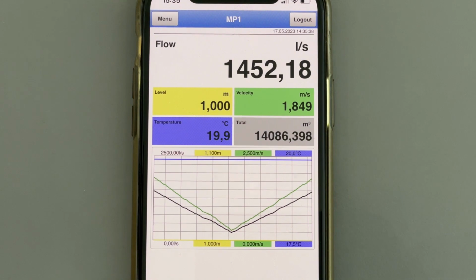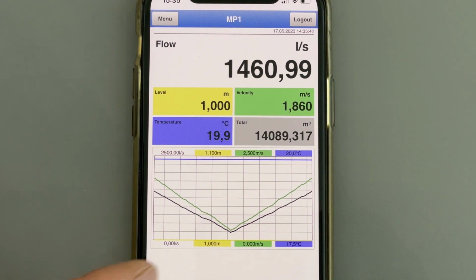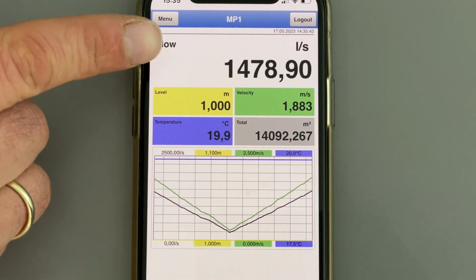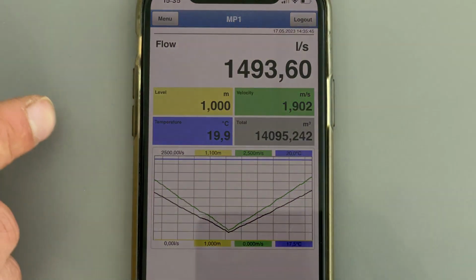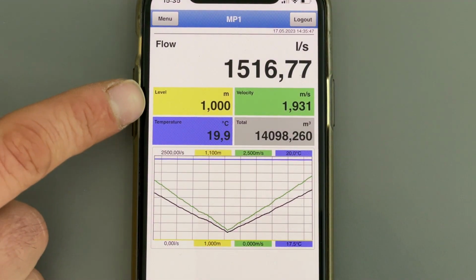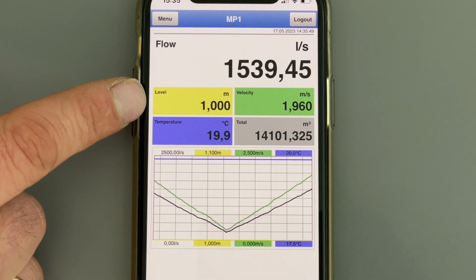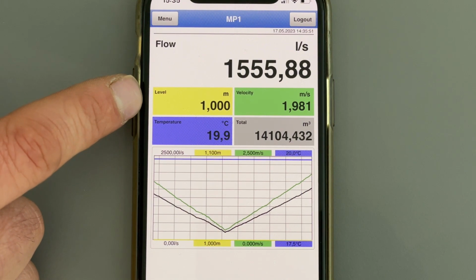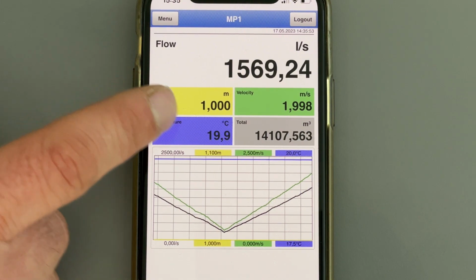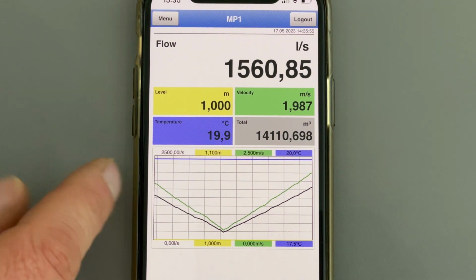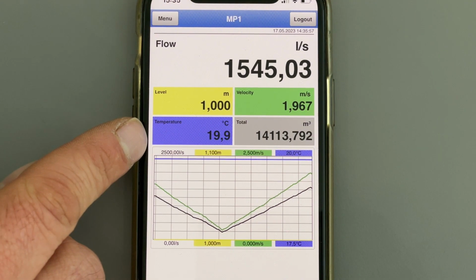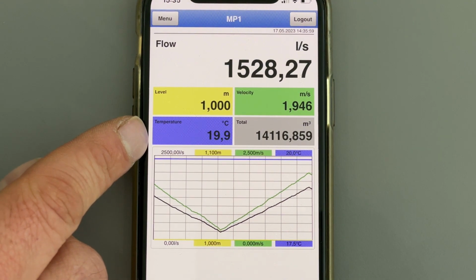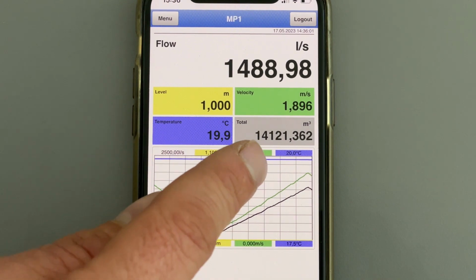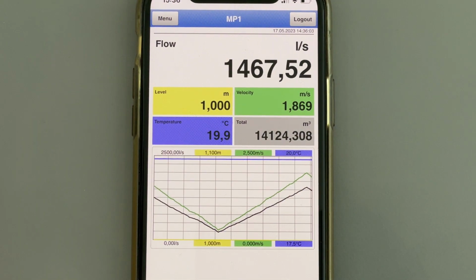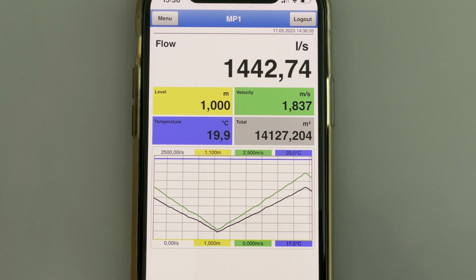When connected successfully to the device, you will see here in the main screen the flow, which is detected by the sensors down at the pipe, the level, which is not a level in this case, but the diameter of the pipe you're measuring at this moment, the velocity in meters per second, the temperature, which is a calculated temperature, not a measured one, and a totalizer for the total volume of water flown through.